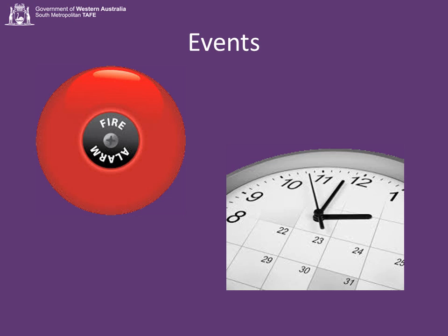Most PLCs have time schedules and a real-time clock, RTC. They normally have a means to program daily, weekly and yearly schedules, with exceptions. That's holidays to you and me, and maybe during the holidays the lights don't come on. There's no real standard to programming time schedules, except that they're always made as easy as possible, since we normally allow the operators to modify them. External events are triggered by inputs such as fire alarms, emergency stops, or maybe a temperature going high.